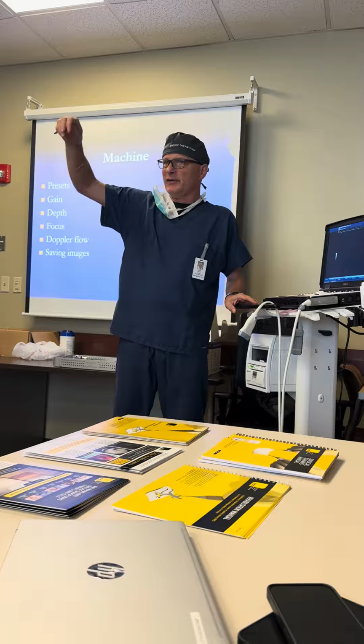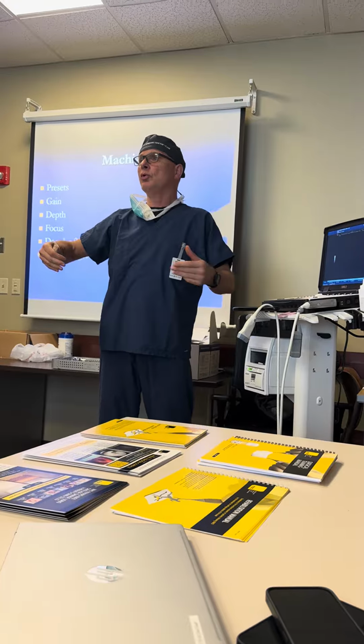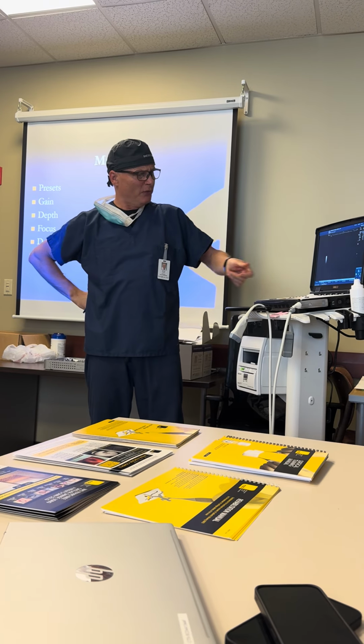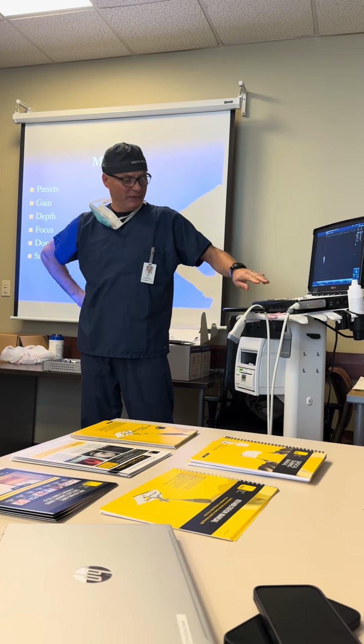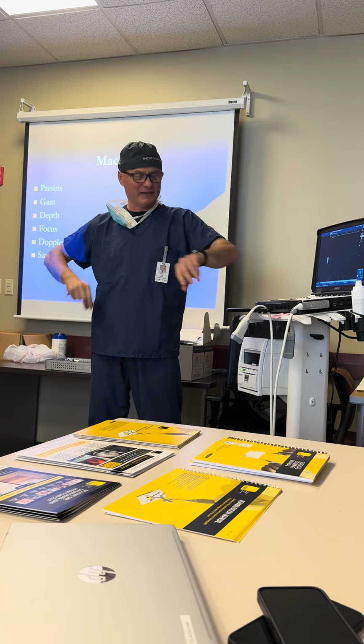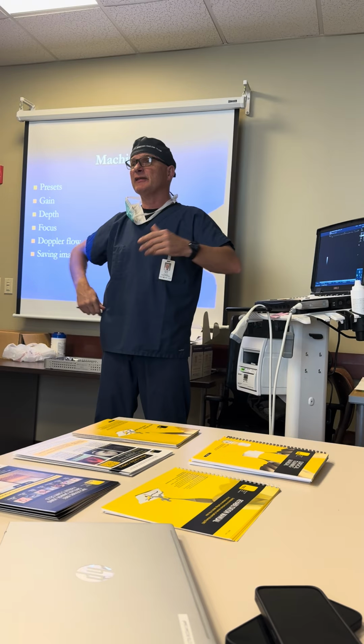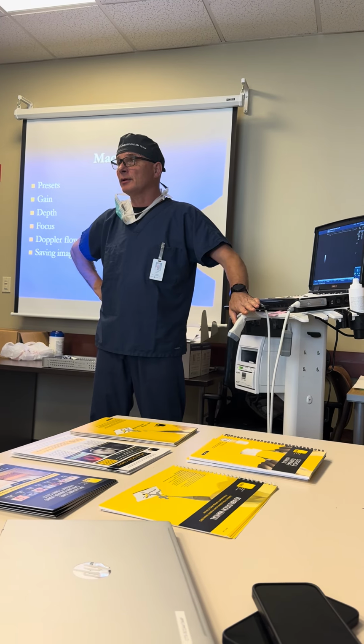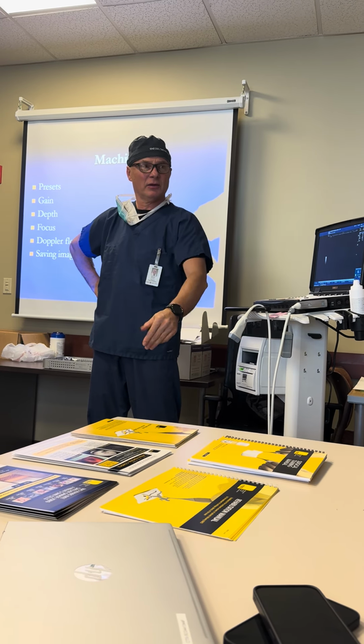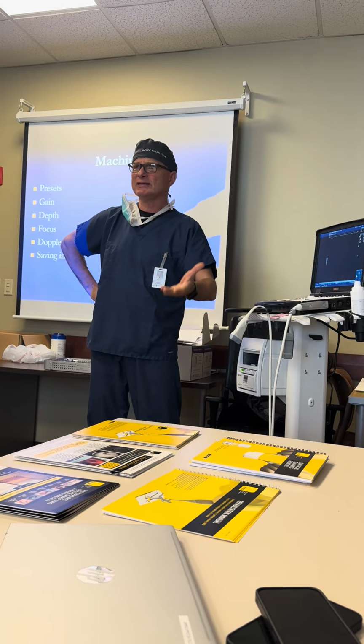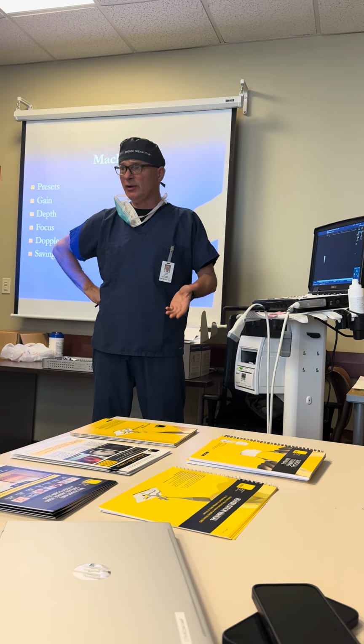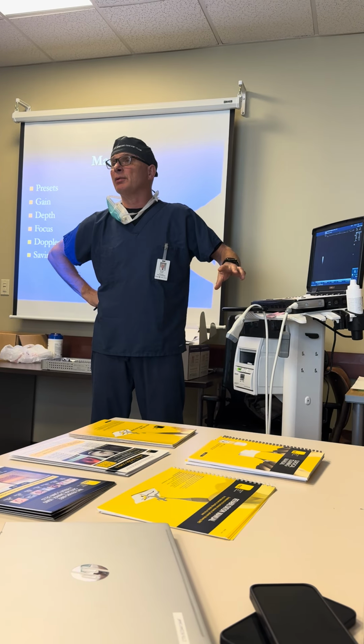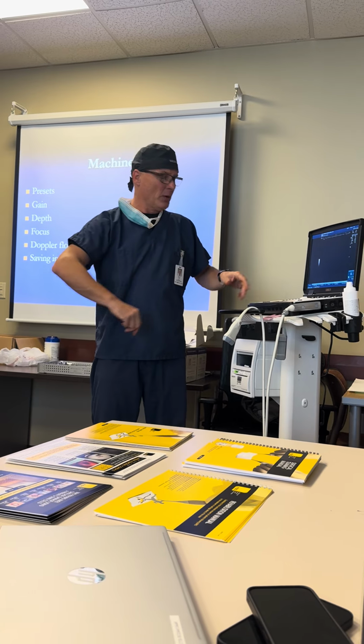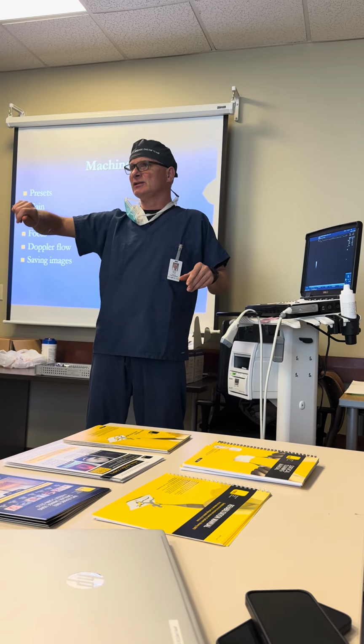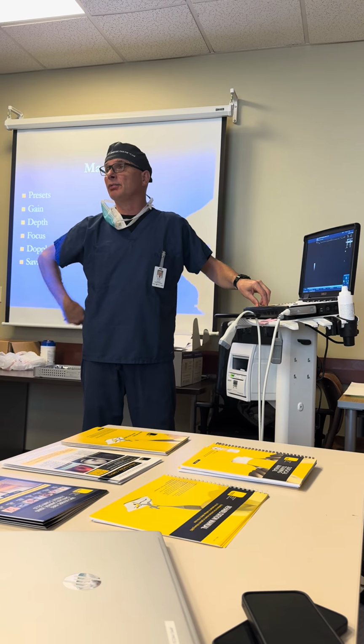Typically, the deeper we want to see, the more energy we need. So if we go deeper with the ultrasound machine, without adjusting the brightness, it gets darker and darker. Because if we send out the same energy from the probe, obviously the more it has to travel, the more absorption we're going to get, so the less energy and information is going to come back to the screen. So we have to increase the brightness. So it is an automatic move. When we are changing the depth with the ultrasound probe, we are adjusting the brightness.